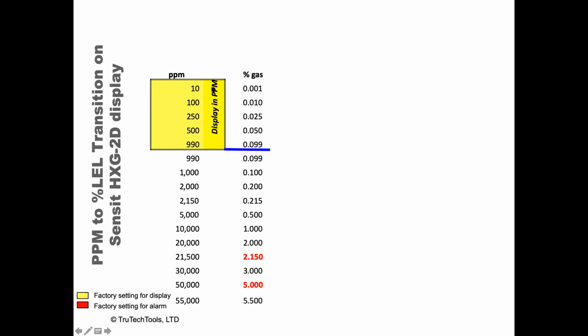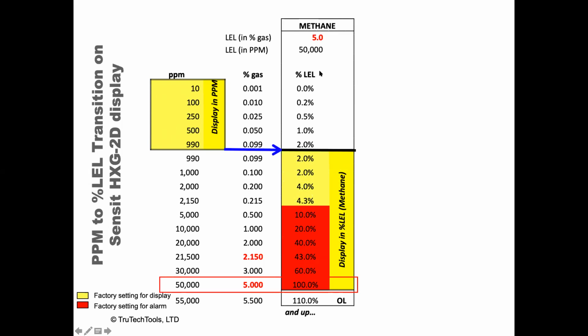The box here shows the unit can be set to display in parts per million up to a certain point, and then it will switch over to displaying in percent LEL. And if it's calibrated for methane, here's where things switch over. So it can switch over here at 2% LEL, which again, the BPI action level for the work you'll be doing is 10%. So you're well within the range here as you move up. But if the meter's ever set differently, this is to give you an idea of the difference here.